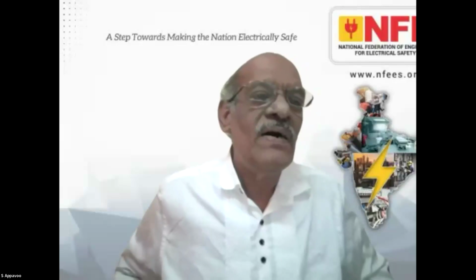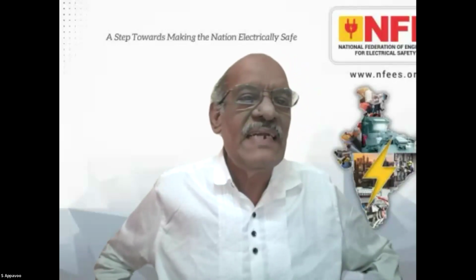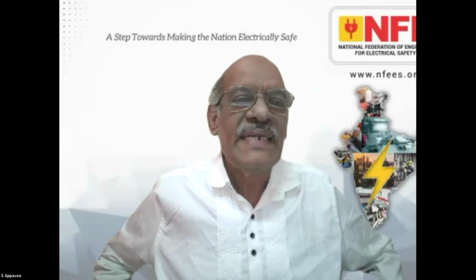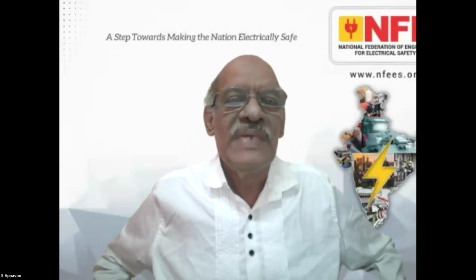Itala Narendra has put a question: can we get a list of equipment segregated based on zones from any code? Actually, you will not be able to get this anywhere - they have not segregated the equipment based on zone. Equipment are categorized into category 1, 2, 3, and 4. You can take the equipment and look in the back of the data sheet anywhere - they'll be putting it category 2 or sometimes 3. In rare scenarios, there will be category 1.